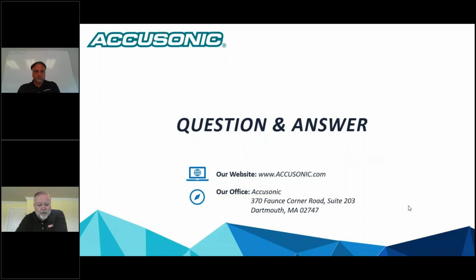So this first question, Guy, is what are the straight run requirements for cross path systems? Good question. As I mentioned before, for going from a single plane system to a cross plane system, ASME PTC 18 does say basically 10 diameters upstream and 3 diameters downstream. For ASME PTC 18 specific applications, they note that you can utilize cross path down to 5 diameters upstream and 3 diameters downstream.